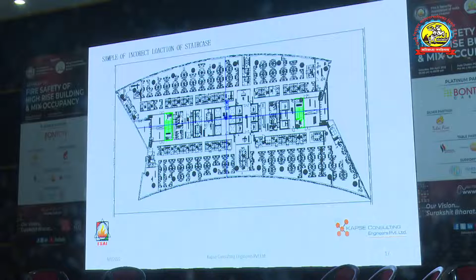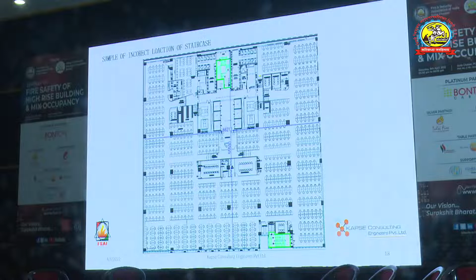Now, one of the buildings that I just surveyed has two staircases. One entry is from here, one entry is from there, so a person here, if he wants to go, has to go to that staircase on the other side. From this corner it is more than 45 meters, and they have put it in the core. There is no ventilation, it's a pressurization system, and the system didn't work. People were coming down the stair, full of smoke, and people panicked. We don't even know how they placed the stairs like this. Is this the way a stair is to be placed? I would have placed it at 4 corners and 2 in the center. So this is the problem.